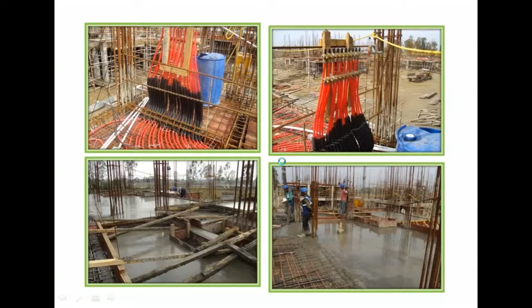The only thing is, when we do the radiant system in a slab, you are having an effect on both sides. That is, you are having an effect upwards, above the slab from the floor, as well as below the slab, that is, from the ceiling of the floor below. But if you construct a false ceiling below the slab, then you are losing the effect which is coming from the ceiling. So when we install a pipe inside the slab, it should be ensured that we don't have any false ceiling below the slab.